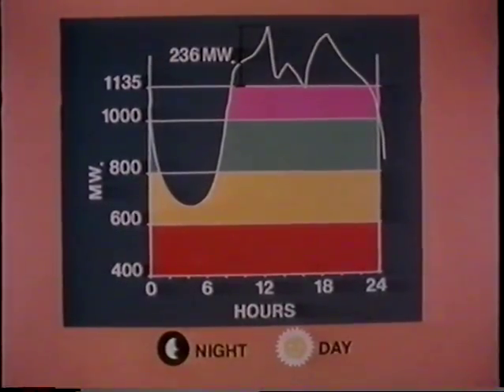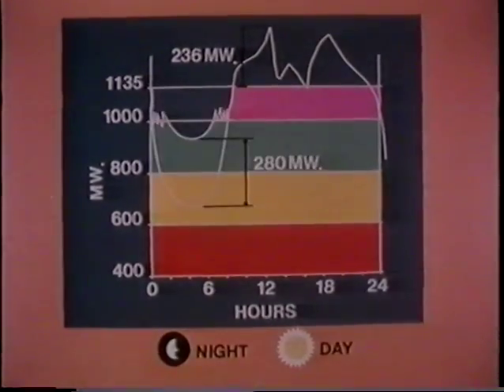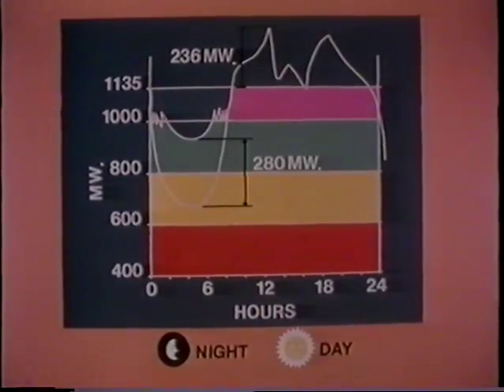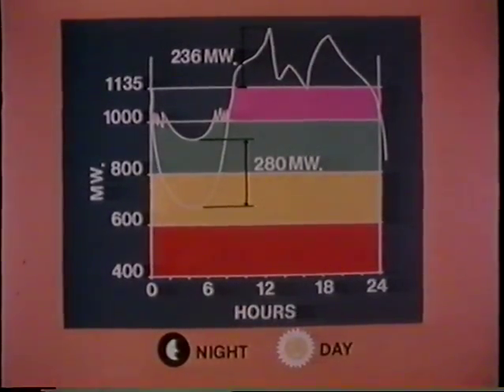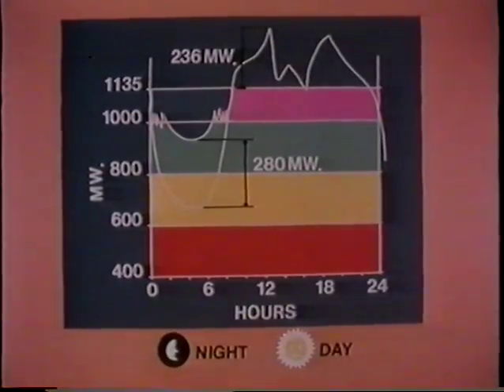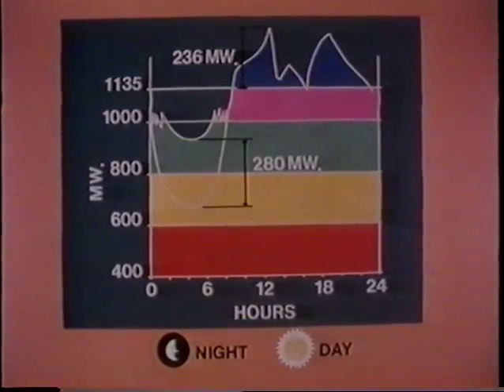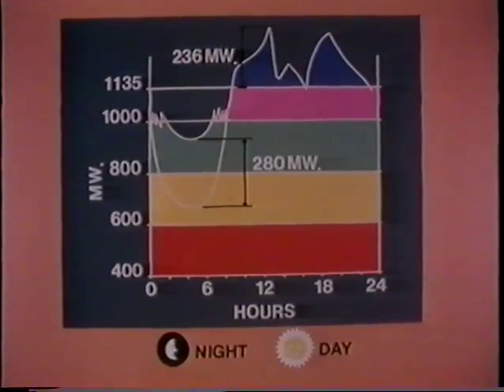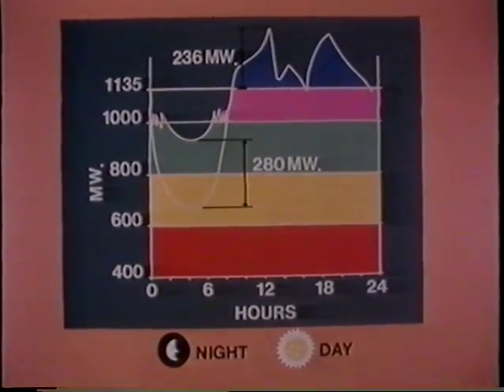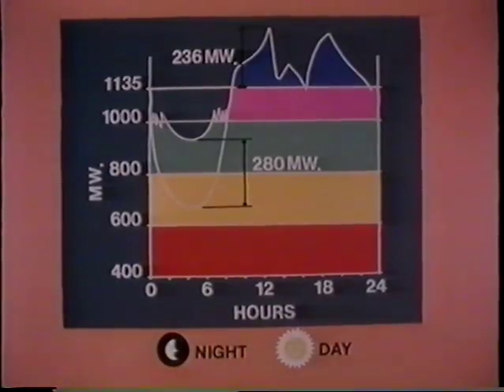Now consider the effect of Turlough Hill. First, during the night, pumping load keeps the most economic stations in operation and thus avoids problems involved in shutting down and restarting thermal plant, which can now be run continuously at maximum efficiency. The resultant gain offsets the loss involved in the pumped storage. During the day, the generating power of the station takes care of the peaks. Here, the advantage of a pump storage system is its remarkable flexibility, combined with minimum cost.